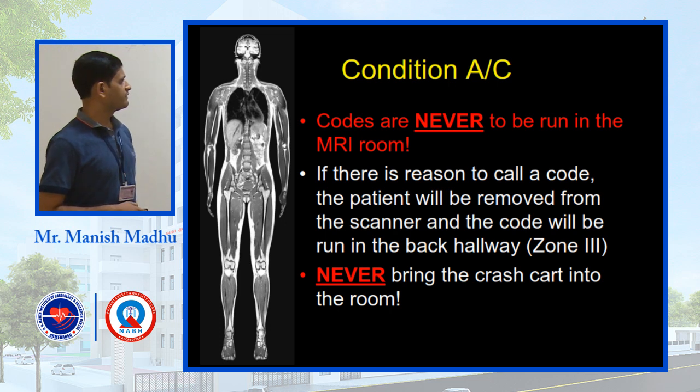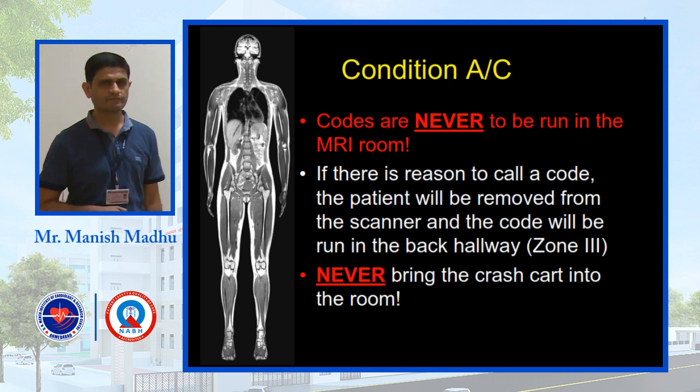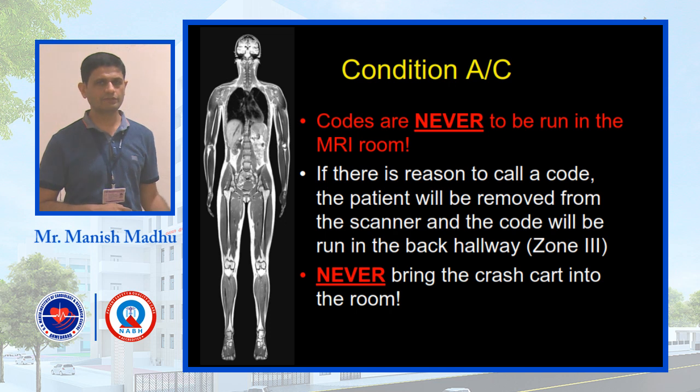Codes are never to be run in the MRI room. If there is reason to call a code, the patient will be removed from the scanner and the code will be run in the back hallway, zone 3. Never bring the crash cart into the room. In an emergency, we always use a crash cart, but crash carts must not be allowed in the MRI room. First the patient should be taken outside to the safe zone, and then we can use an MRI crash cart only.